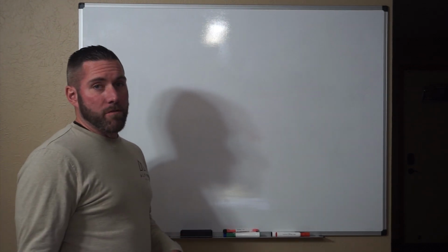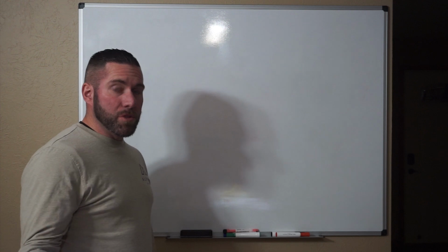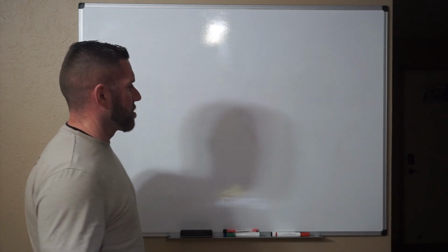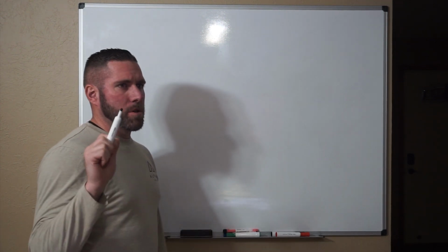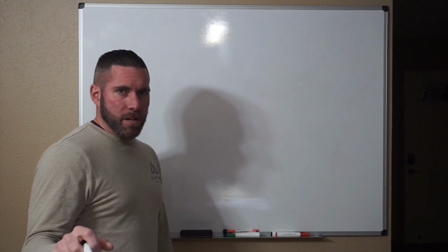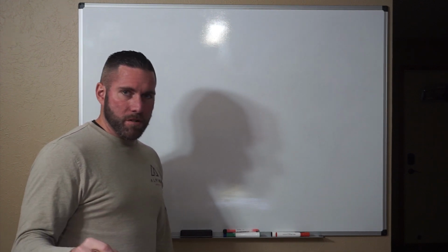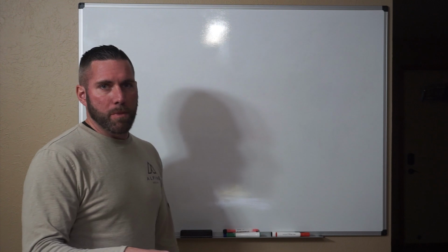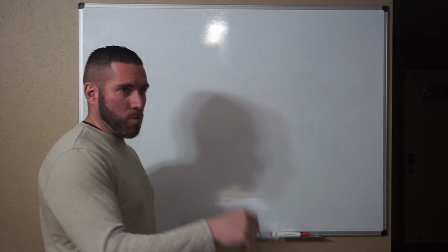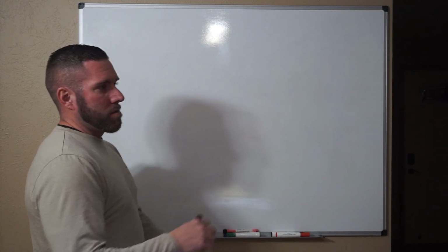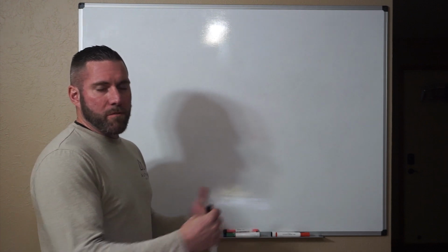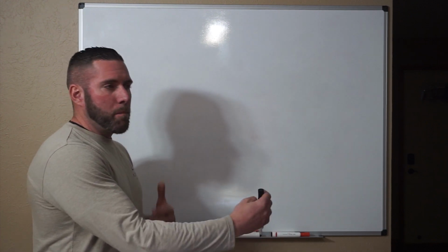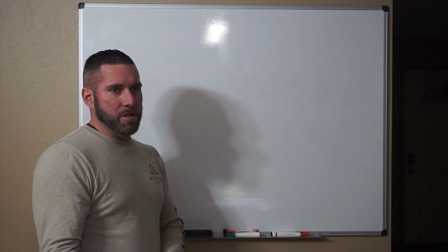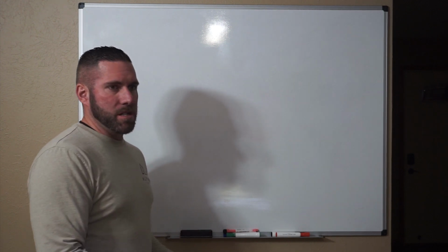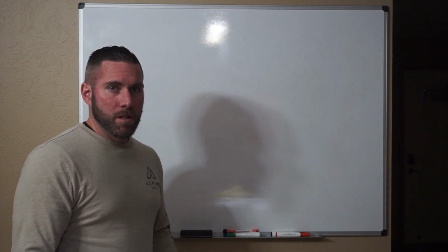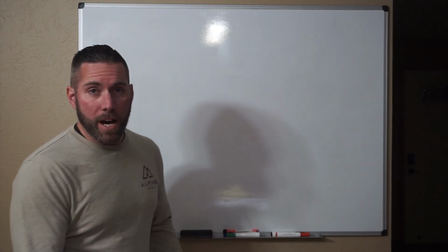Alright, so today we're going to go over sensor types and how to choose the correct sensor for a control system. One of the questions that came up was, how does a data sheet tell you, other than input or output signal type, how a sensor should be matched to a system on what you're actually measuring? Like, you could have a proximeter that measures anywhere from 0 to 12 inches, but because you're measuring something that goes from 0 to 12 does not mean that that sensor is viable. As a matter of fact, it's entirely the opposite.